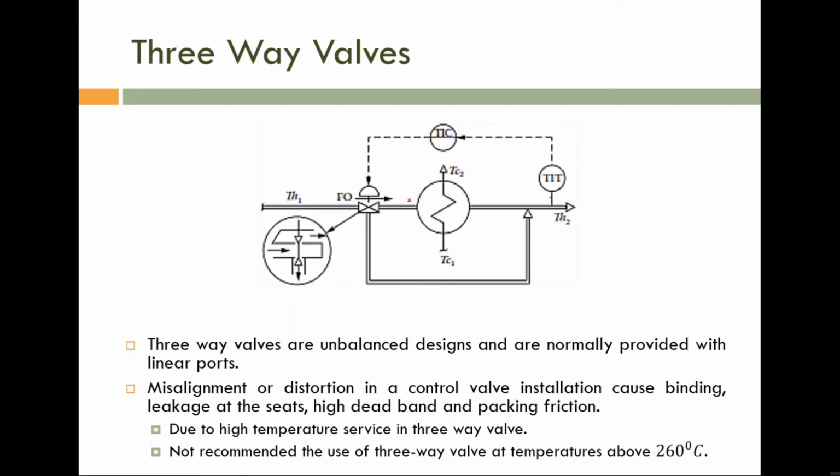Now we are going to discuss the disadvantages of three-way valve. If you are using three-way valve, the main disadvantage is that this one is an unbalanced design. We can decrease that by using linear port, but we can't remove that problem. The three-way valve is an unbalanced design. That is one problem.